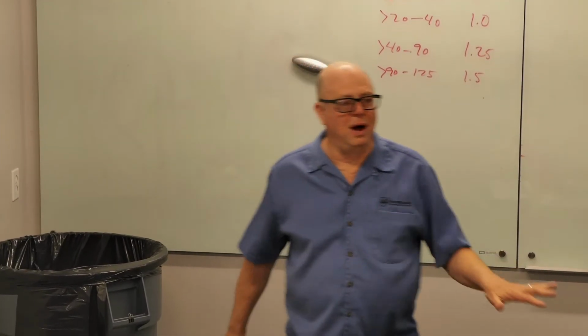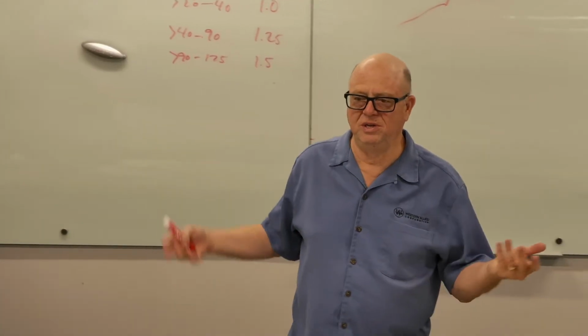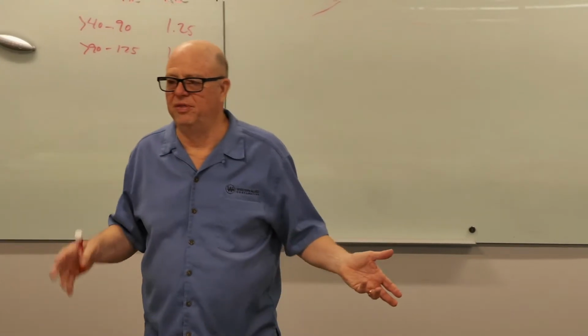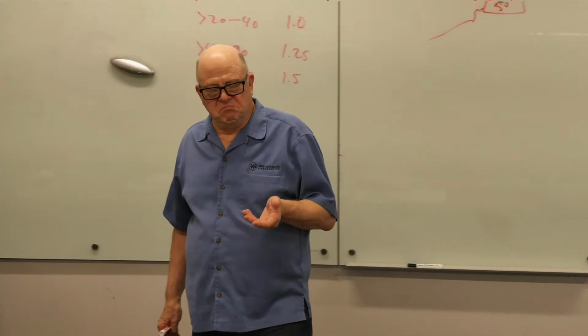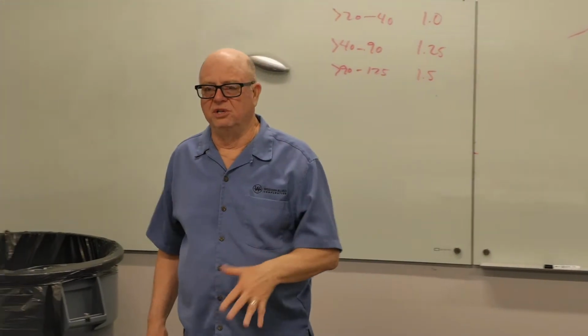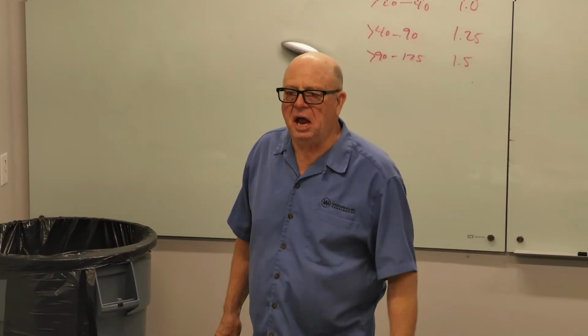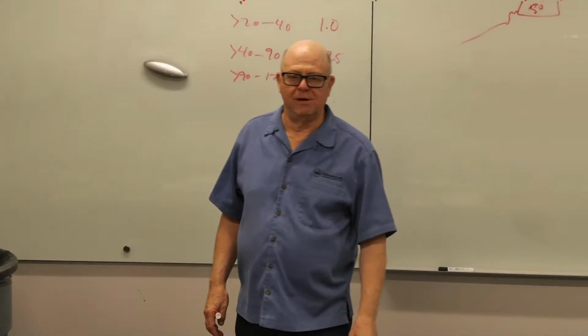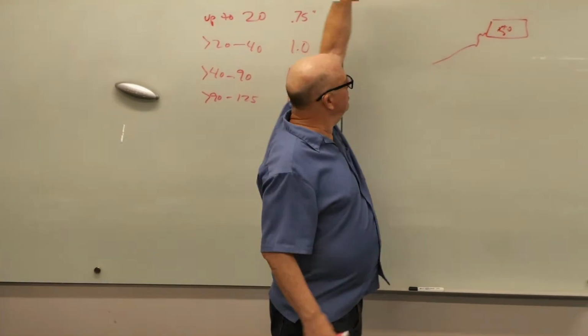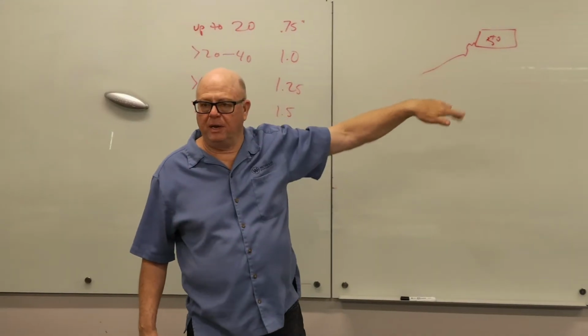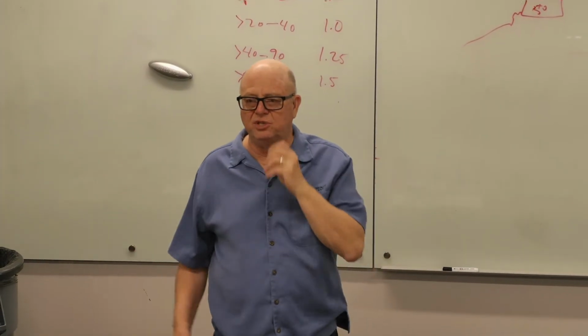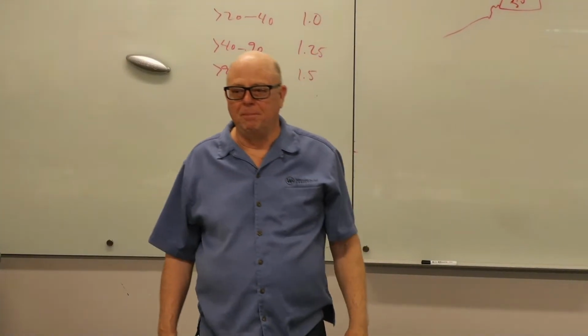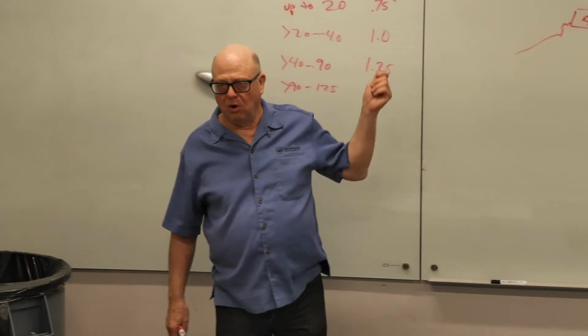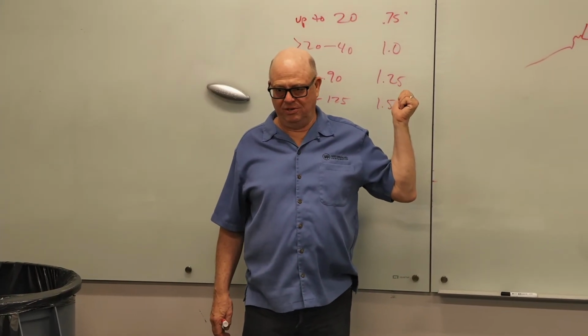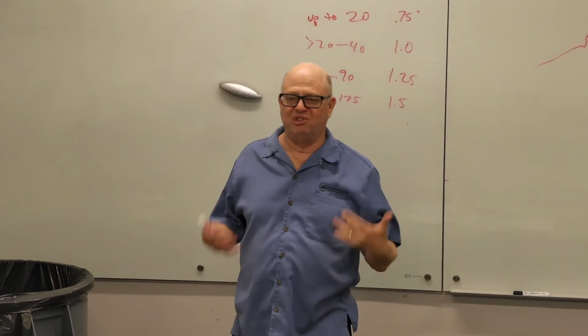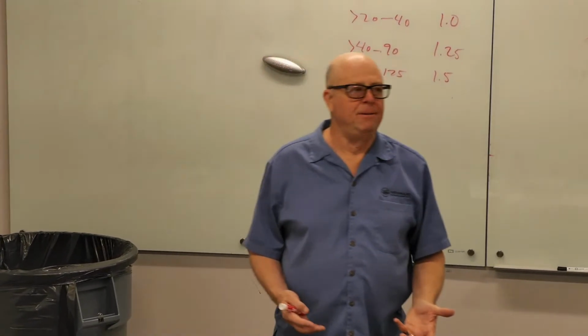We had no problems for years. I told you we did this in like '01 or '02, whenever we did that. But a dozen years ago, it started getting humid in early July. And there was more humidity in the outside air being brought in, and so there was more condensation. And pretty soon, we're overflowing a couple of these lines because the drain line size is not enough.